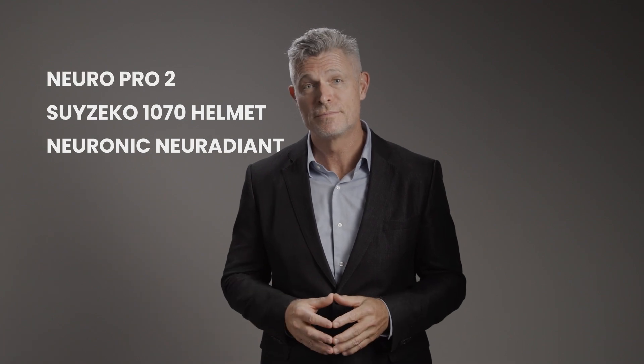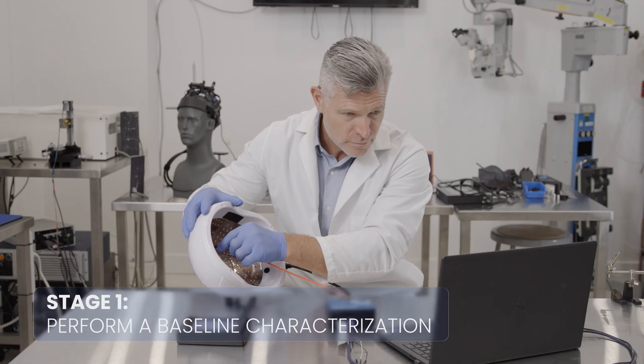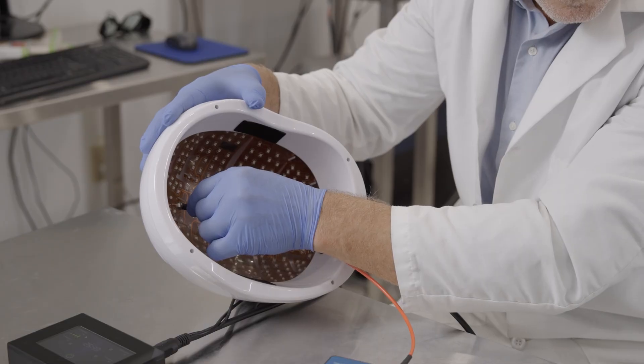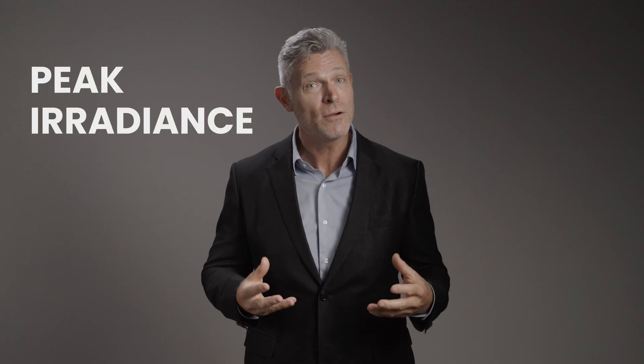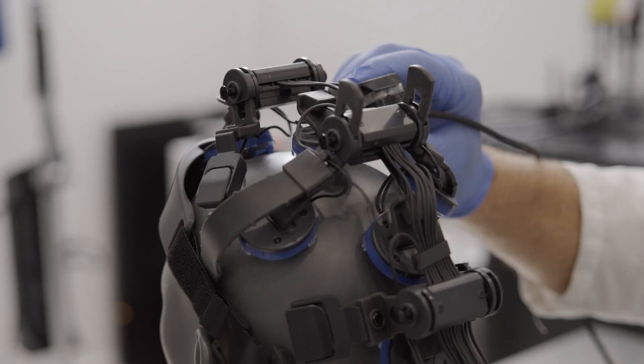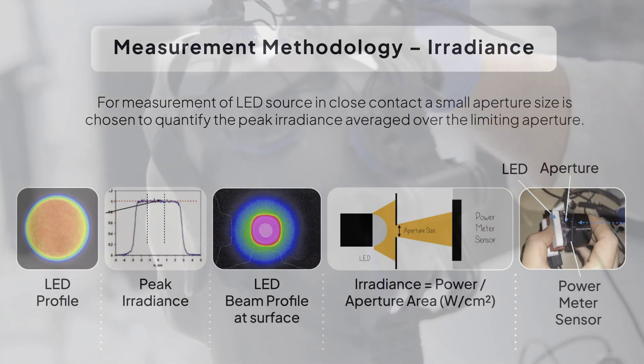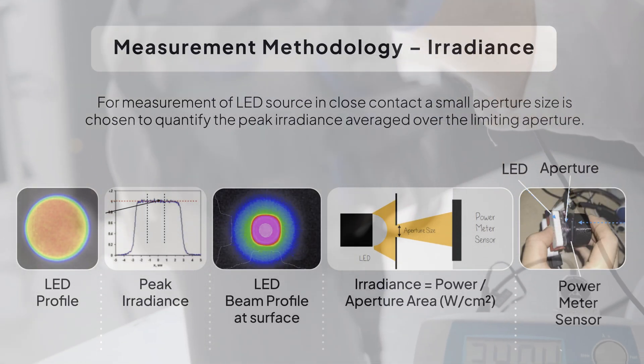Our procedure involves three key stages for each device under test: the Neuronic Neuradiant, the Suyzeko 1070 helmet, and the NeuroPro2. First, we perform a baseline characterization with the spectrometer and power meter. The spectral irradiance is measured at multiple locations on the emission surface to determine the peak irradiance and peak wavelength. With the power meter, to convert the value with a 1 mm pinhole into a metric suitable for irradiance, power is divided by the area, given by πr².